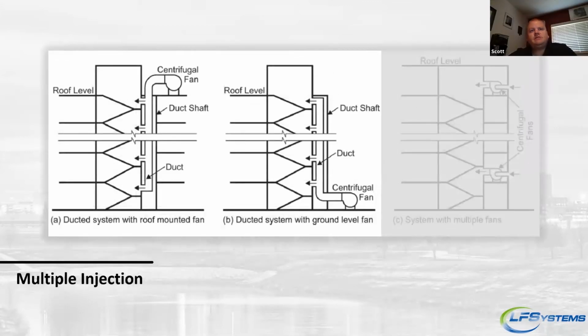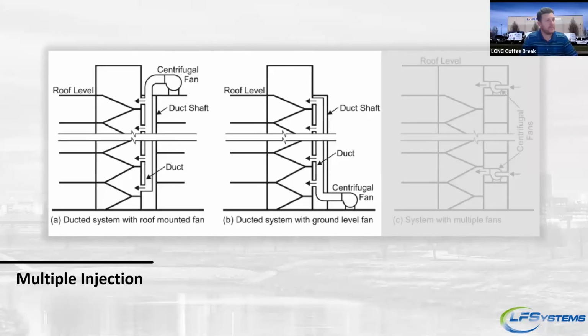The other type of system is a multi-point injection system, where you have a centrifugal fan either on the roof or ground level, injecting at different points. If I understand it right, this is fairly common up in the Denver area, isn't it? Yes, absolutely, Scott. On a lot of the past projects I've worked on, the multiple point injection technique is very common. This could have a pressurization fan and or exhaust fan, modulating relief dampers, and control system devices comprising manual pull alarms, smoke detectors, safety switches, transducers, and of course, life safety dampers.